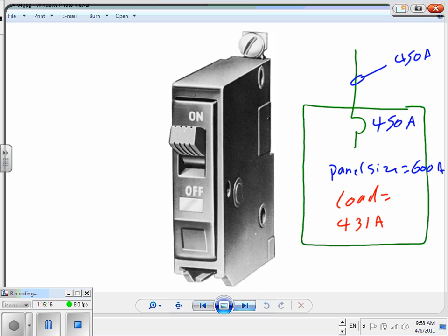Is it wrong to make the circuit breaker 600, and then the cable has to be 600? No, but what's the issue with that? Money. And we talked about this one, guys, that from 10 to 15%, if you're around it, go up. But this is judgment, I guess. If I was close to 600, I would use 600. I'm way far away from 600 based on my load. And guess what? My load, Spencer, already took into consideration 10 to 15% future expansion. You have to think about this one: have I taken future expansion into consideration? Yes, Chad, I already took future expansion, and I came up with 431 amps after I applied it. Should I go to 600 also? That would be overkill.